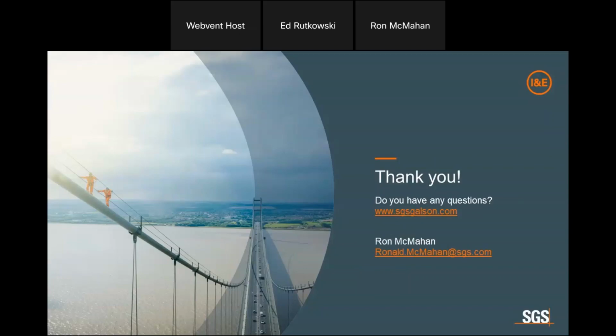Okay, Robert asks, was there any field calibration done in addition to the annual lab cal? So the units, when we put them together in East Syracuse, we did the assembly, we did calibration in Syracuse. They were installed in the field and we checked calibration at the outset. During that process, we have all that data and what the readings were. And again, we were using plus or minus 20% for fail or pass. And we have all that data.